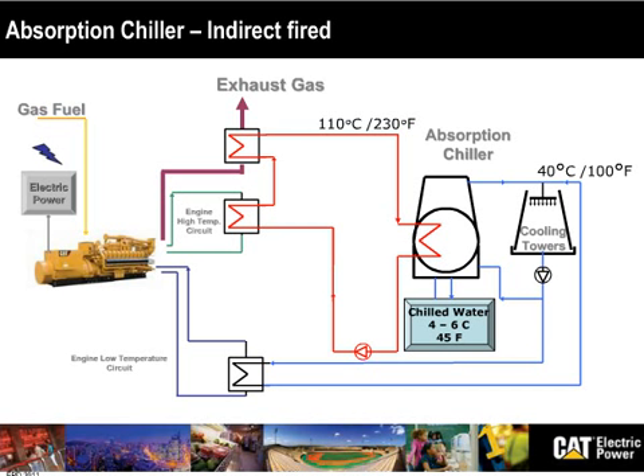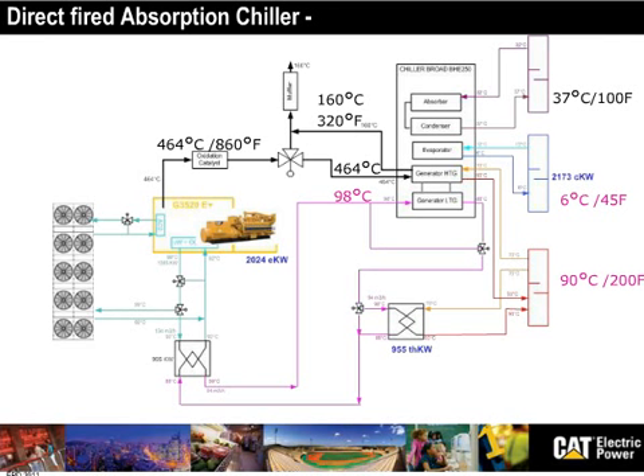chilled water. And to do that, we feed an absorption chiller. I don't want to go into details of the absorption chiller technology, but it's a machine that you feed with heat, and it gives you cold. So typically, the cold you can obtain with an absorption chiller is 45 F, 4 to 6 degrees C. And to do that, you have two technologies. Either you use the hot water or very hot water we can send to the absorption chiller, like in the chart here, or you can directly send the exhaust gas inside the absorption chiller. The hotter the media, the more efficient the absorption chiller. So that's why there is an advantage to use the exhaust gas directly.